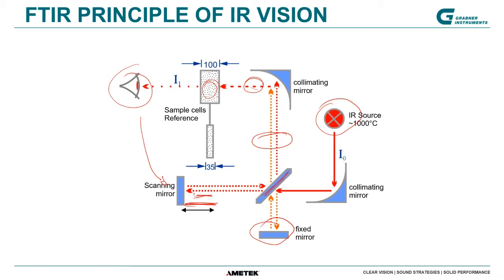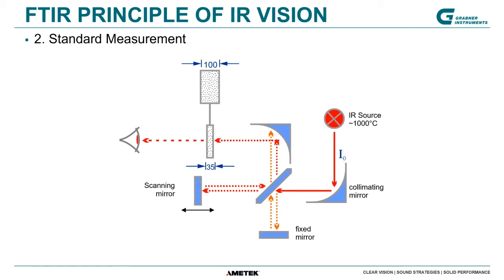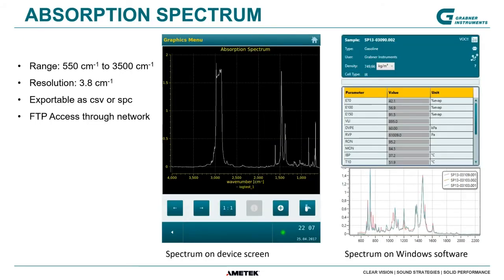The setup of our instrument uses three different cells. You see here the 100-micron cell and here a 35-micron cell. In the first run, we do a scan of the window just to get a reference scan. In standard measurements, we scan through the 35-micrometer sample path length, which is applicable for most fuels and samples. But for certain standards — especially for jet or diesel standards — we also need to use the 100-micron cell. What you finally get after transforming your interferogram is an absorption spectrum.